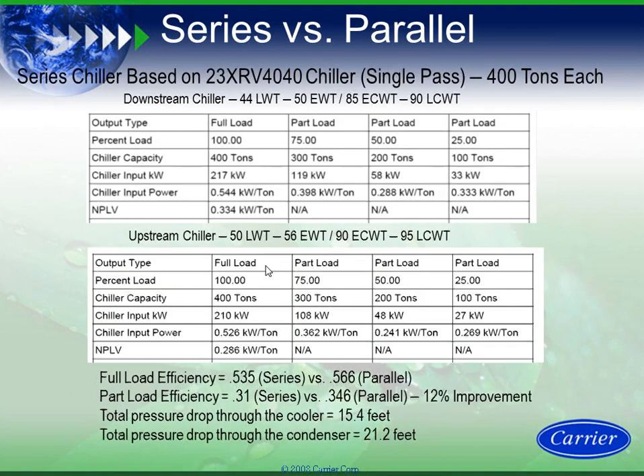I now take this and I go to a series 23XRV 4040. The cost didn't change on the system. Okay, it's the same cost whether I go to a 2-pass chiller or a single-pass chiller. You're talking about the same exact cost for chillers. So now my downstream machine is 0.544 full load, 0.334 part load.